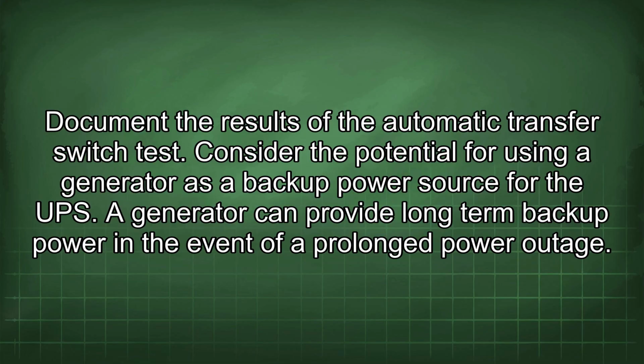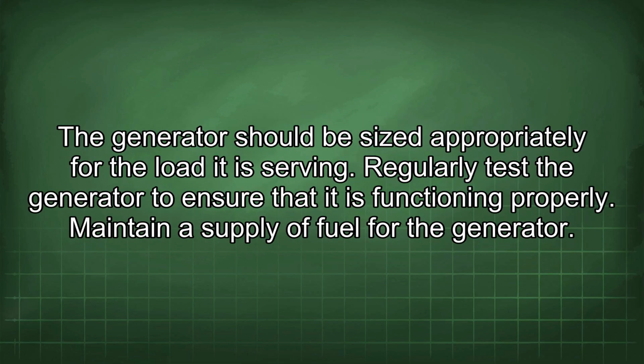Consider the potential for using a generator as a backup power source for the UPS. A generator can provide long-term backup power in the event of a prolonged power outage. The generator should be sized appropriately for the load it is serving. Regularly test the generator to ensure that it is functioning properly.